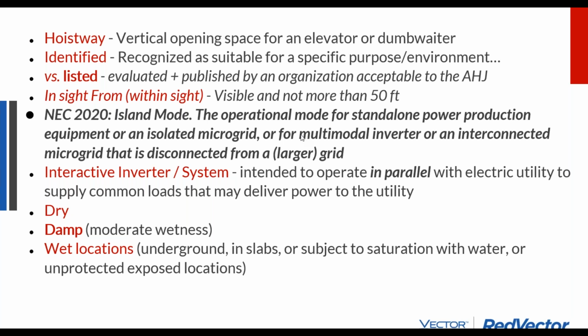Let's see, within sight or visible is restricted to 50 feet. Sometimes with these disconnect requirements, you get buildings spaced further apart, like a solar array on a barn going back to a house. That visibility requirement is really there so that it's not over a long distance. Even if it's visible over a long distance, there's a limit to your visibility. One way to think of it is that if someone had 20/50 vision, which is not very good, they could still see that disconnect switch no more than 50 feet away.